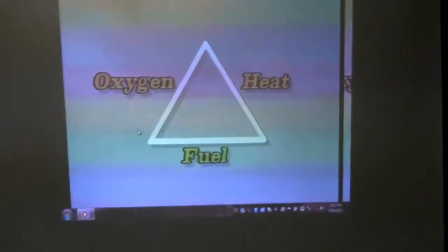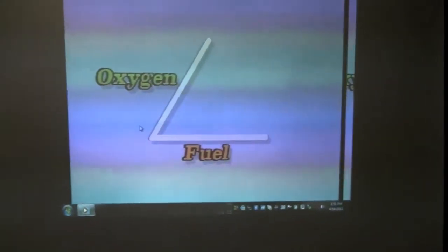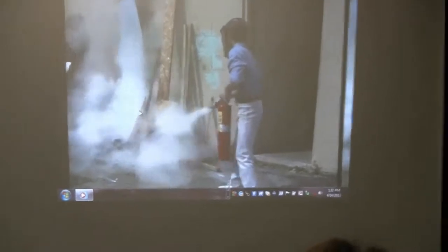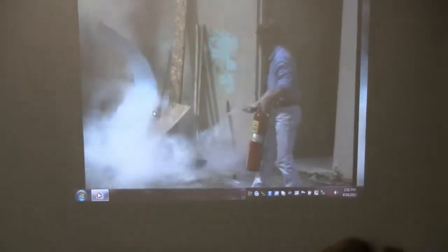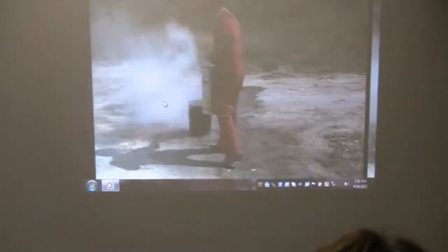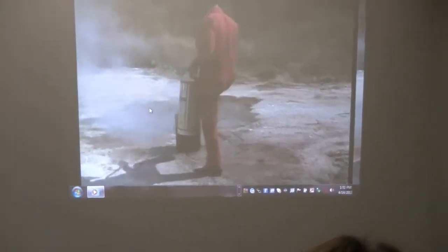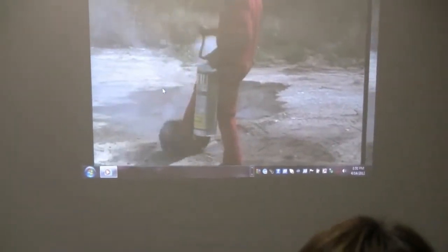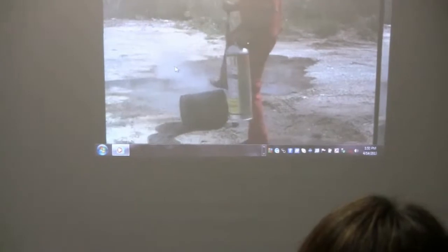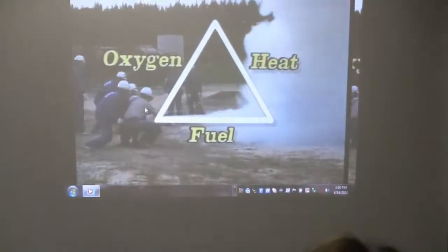Class A extinguishers remove the heat element of the fire. Class A fires form embers that will continue to smolder if unchecked. Always make sure a Class A fire is totally extinguished and remove the materials from the building after they are extinguished. Class B extinguishers work by smothering. The dry chemical shoots out a powdery cloud to smother the fire.